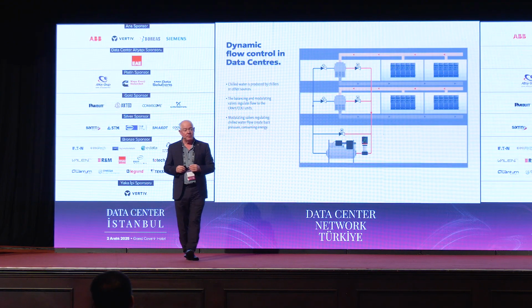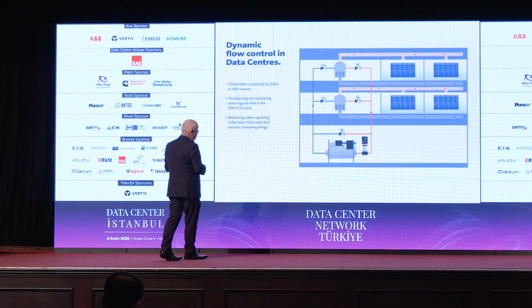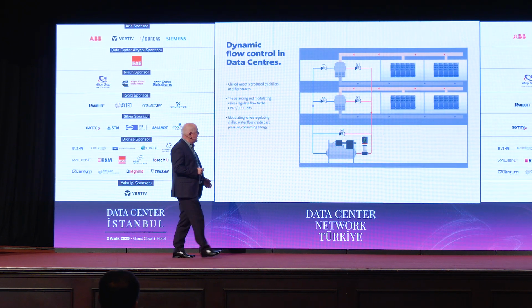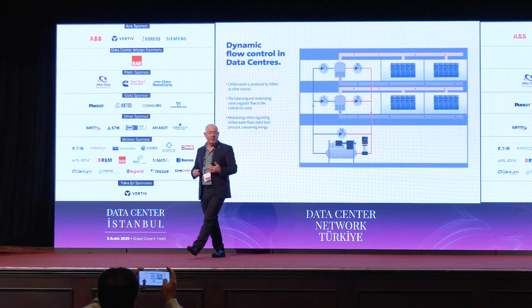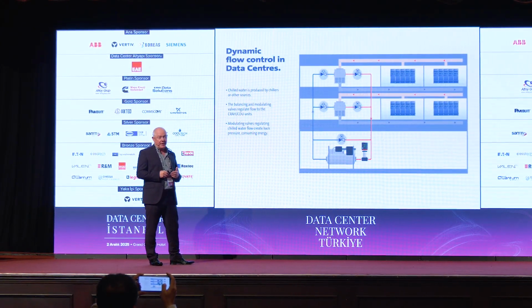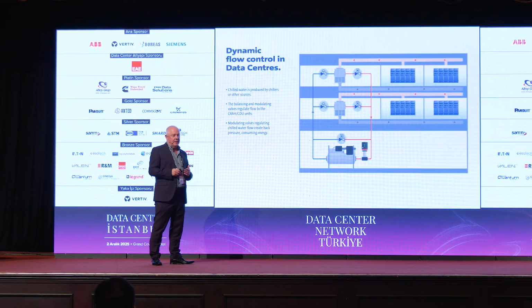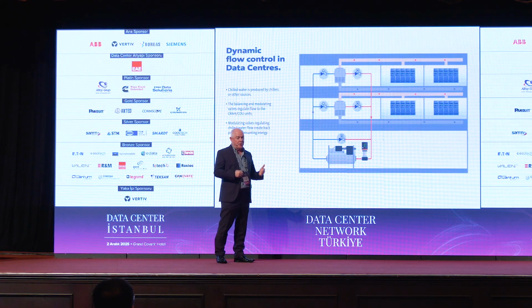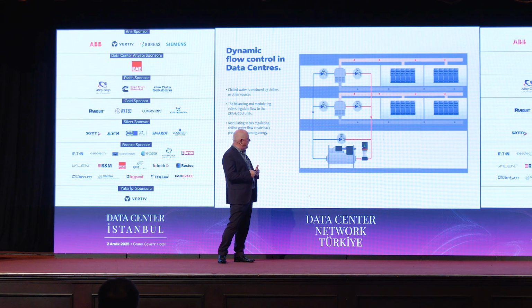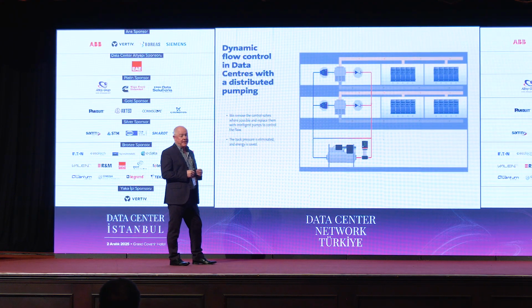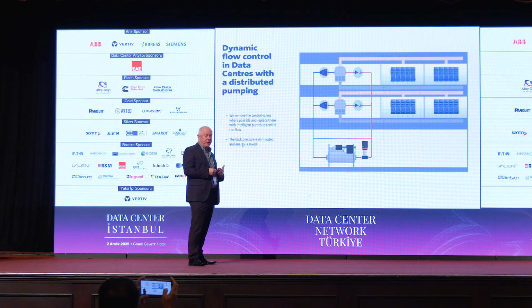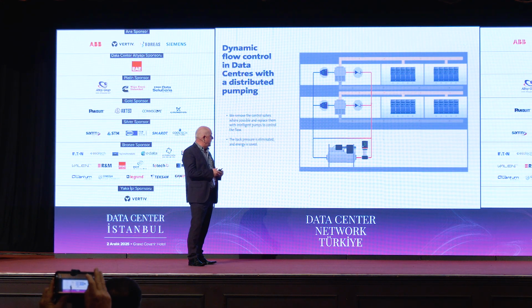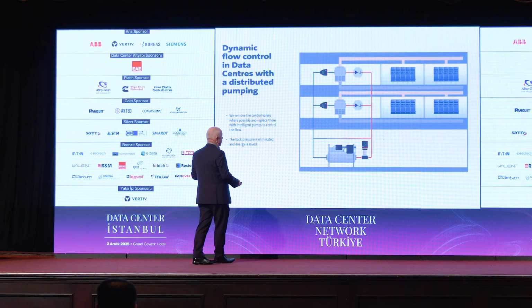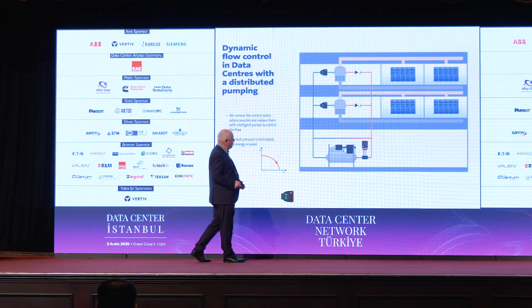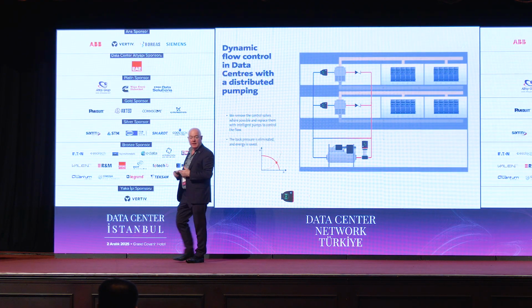So if we look at distributed pumping and how we get water around a data center or any other type of cooling application, basically we've got a chiller plant and we have valves which are opening and closing, and those valves are controlling the amount of cooling going to the different applications. The difference that we would like to look at with distributed pumping is, instead of opening and closing valves, which cause a lot of energy, there's friction losses and we need more energy to get across those valves, we look at using smart, intelligent pumps. And those pumps have variable speed drives built in. Taking out the valves, we reduce the friction loss in the system, so we need less energy to pump the liquid around. And we also balance the secondary and the primary sides, and I'll go through how we do that now.